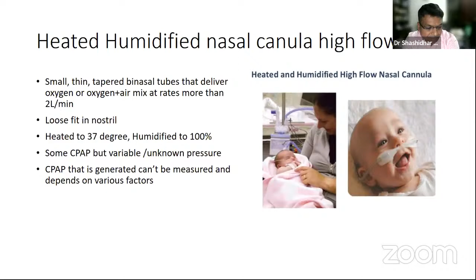Now, how does it work? I'll come to the next slide, but basically it does generate CPAP, but there's no way of measuring it, and it is variable. The pressure can be anywhere from 1 centimeter to 8 to 9 centimeters of water, and it depends on various factors: the size of the prong that we are using, the size of the baby, whether the mouth is open or not, and also the flow rate. All of these will determine how much CPAP is generated.